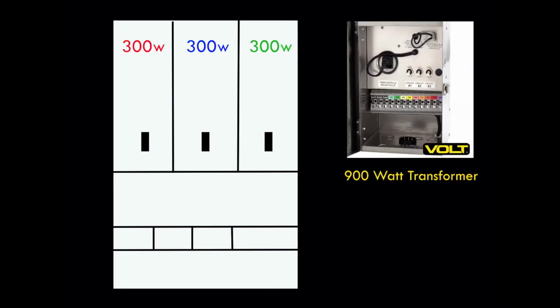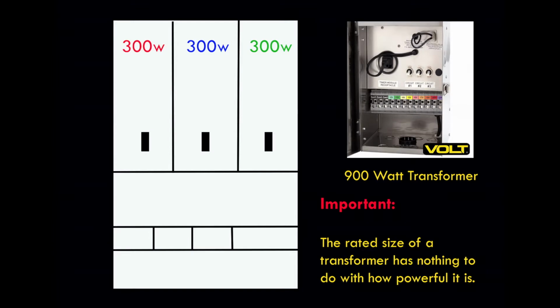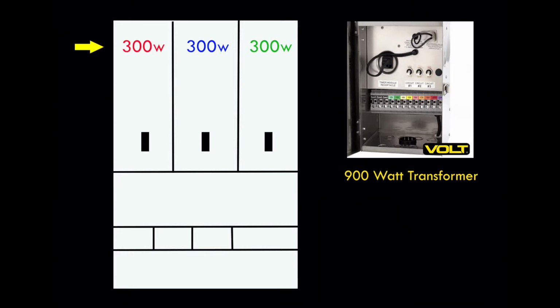Now we can look at our transformer in much the same way we did the computer. We have 3 individual 300 watt units that make up a 900 watt transformer. Just like our 900 gigabyte computer was no more powerful or faster than the 300 gigabyte computer, our 900 watt transformer is also no more powerful than a 300 watt transformer. If you remember, the rated size of a transformer has nothing to do with how powerful it is. The greater size of the transformer simply means that we can put more lights or more wattage on this bigger transformer. Looking at our transformer, you can see that we have 3 300 watt transformers stacked side by side, which make up our 900 watt unit.